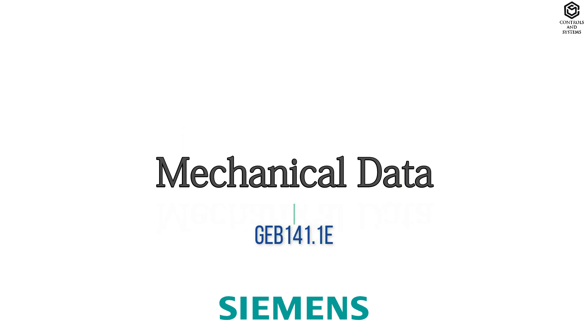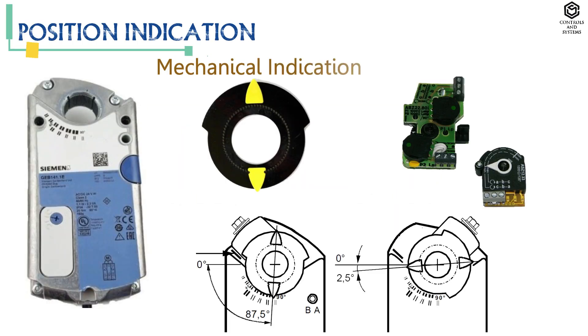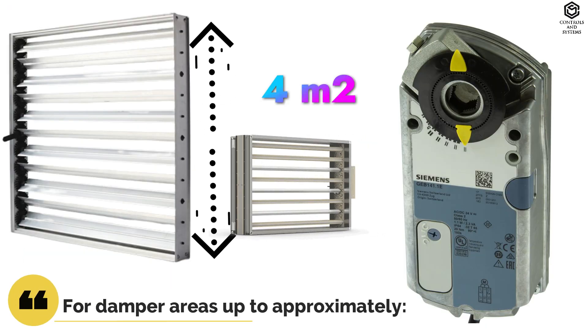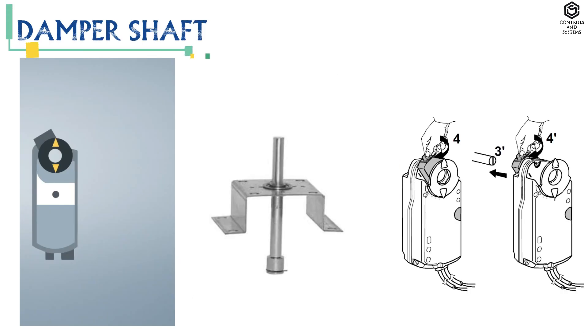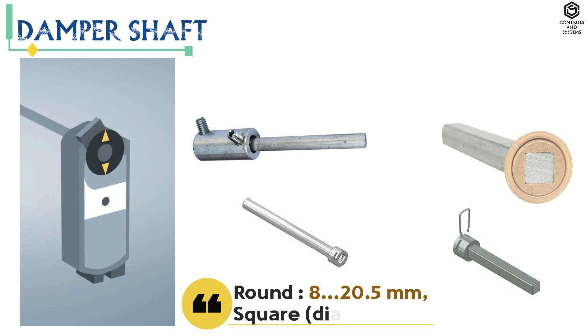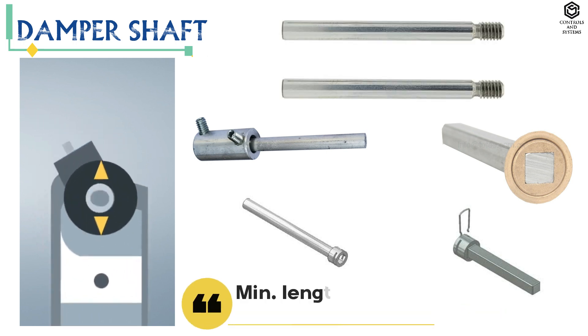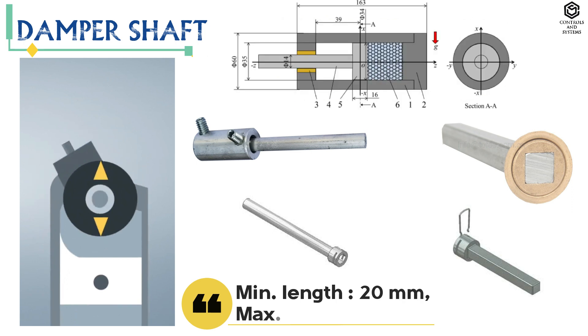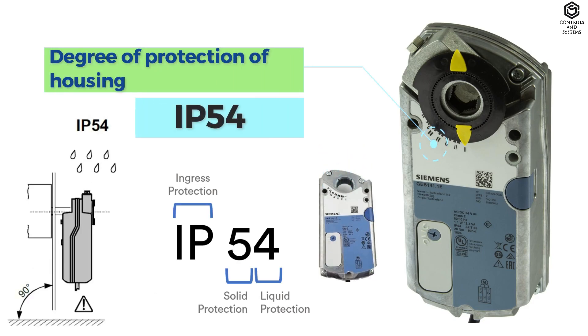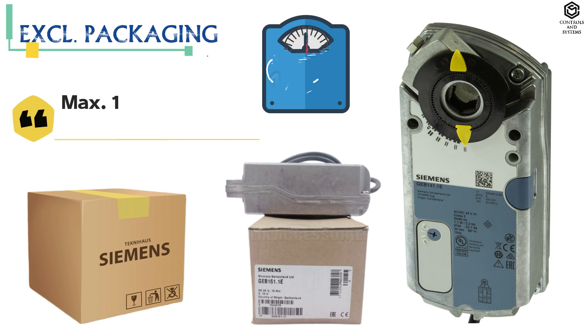Mechanical data: position indication is available in mechanical and electrical formats, for damper areas up to approximately 4 square meters. Damper shaft: round is 8 to 20.5 millimeters and square is 8 to 14.5 millimeters. Minimum shaft length is 20 millimeters, maximum shaft hardness is less than 300 HV. Degree of protection of housing is IP54.